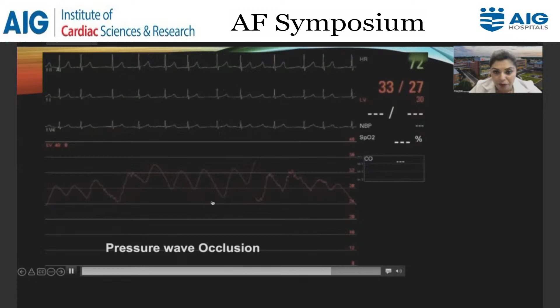For example, here you had a small A wave, so I'm moving the balloon. You can see there's some noise on the screen. And once I've achieved that occlusion, right there, you have that clean V wave signal that tells me that I have adequate occlusion. So I confirm this, and I confirm my location of the balloon on ICE before I come on the freeze. I also make sure that I have adequate proximal seal before I come on freeze as well. So again, demonstrating that pressure wave occlusion that we see with the balloon.